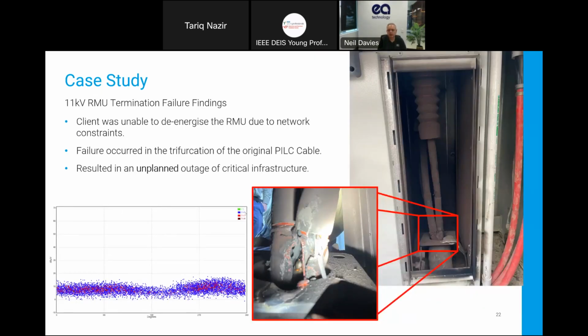We look at the picture of the failure. The reason it wasn't acted on was that it's actually quite a difficult one to take off due to network constraints. It's that balance between probability of failure versus network disruption. Can I wait for my next outage? Can I wait for the next annual shutdown to come along or not? In this particular case, the decision was made to wait, but unfortunately in a 7-month period it failed.